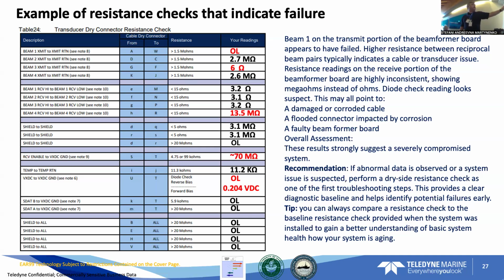And then we have the receive enable ground here, where you're supposed to have either 4.75 or 99 kilo ohms, and now we got like 70 mega ohms. There's definitely something going on. Not happy with this system there. You're probably lucky to have power. And then we look at our diode check, at which point is open, which can be fine, but the 0.20 volts DC, that's way low. So again, you probably don't have power at this system. So it's all just little things to look at.